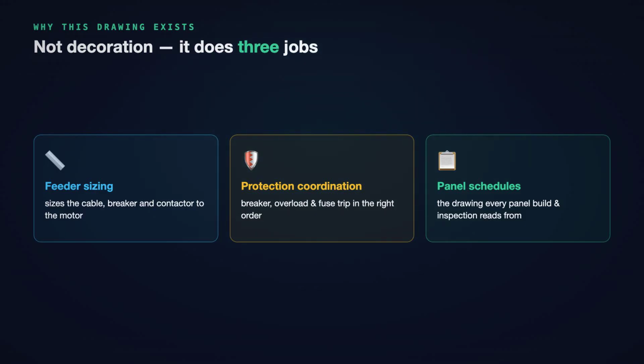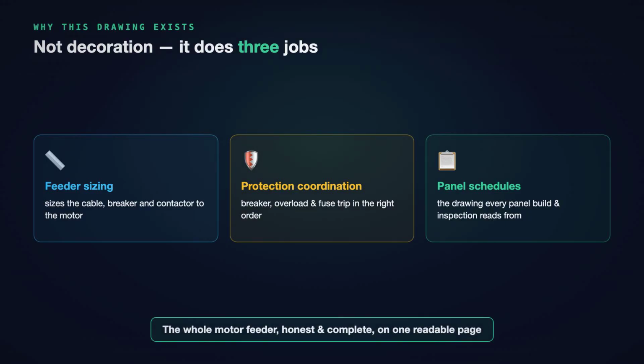And it earns its place. It does three things. It sizes the feeder, the cable, the breaker, the contactor, all matched to one motor. It sets up protection coordination, so the breaker, the fuse, and the overload trip in the right order, not against each other. And it is the drawing your panel schedule and your inspection are read from. That is the promise of the motor single-line diagram. The entire starter, honest and complete, on one readable page. So let us follow the power.